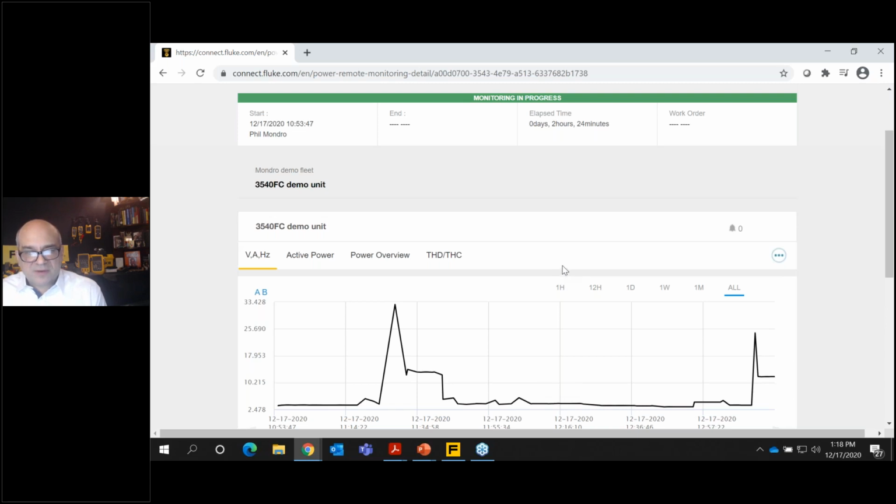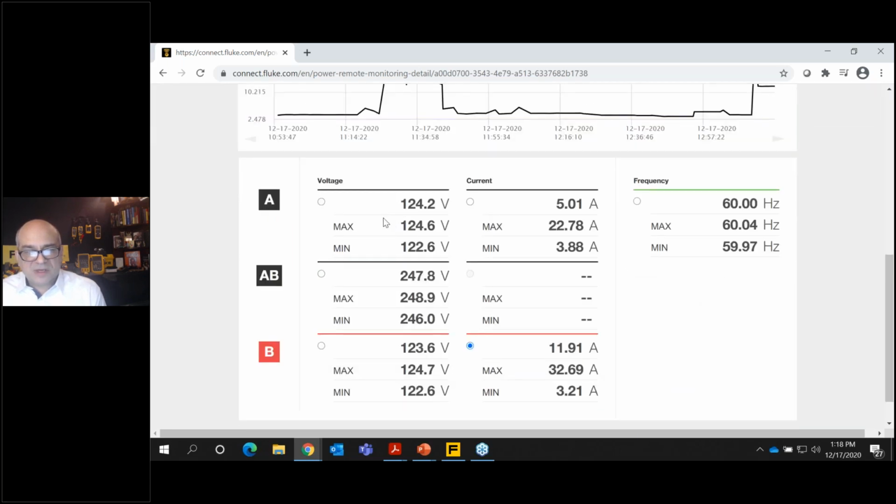Now, when we talk about power, we start with, what's going on voltage wise? Do you have good voltage coming in? Is it balanced? And we don't always talk about over voltaging, but it's also very important depending on where you're at geographically. A lot of things industrially are not designed to run on more than 480 to 485, 490 volts.